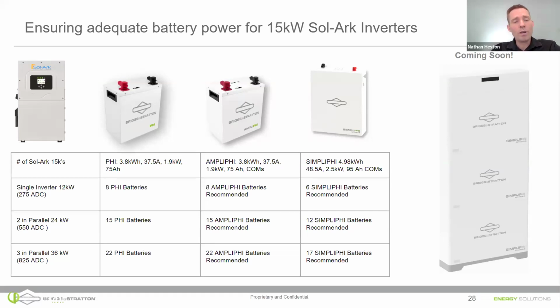However, to keep your warranty, you need to program that inverter appropriately so that you're only drawing the amperage that the batteries allow. Those 48-volt Phi batteries allow you to draw 37.5 amps continuously per battery. So yes, you can go smaller, but you'll need to program the inverter appropriately. And we really recommend going with that minimum number of batteries.